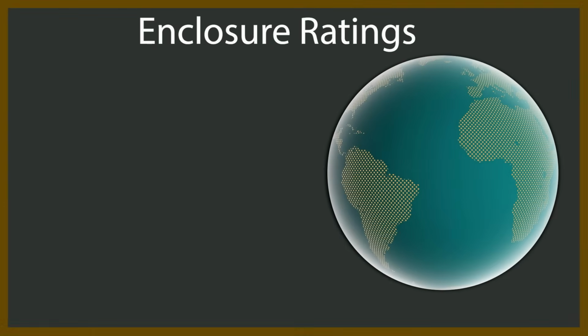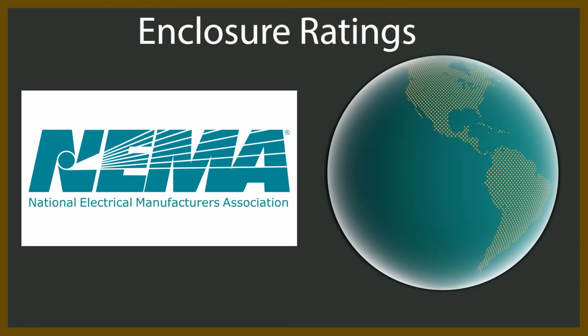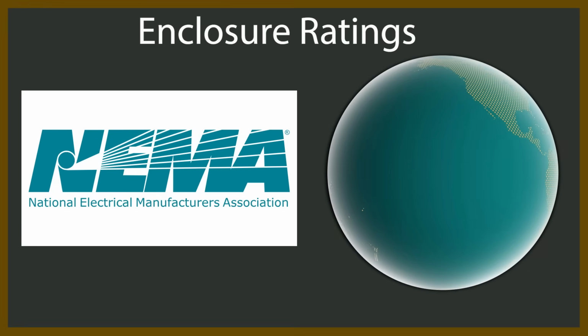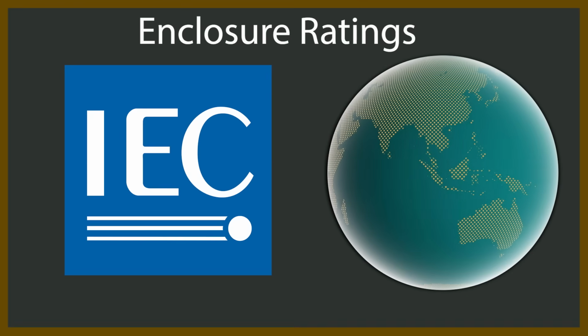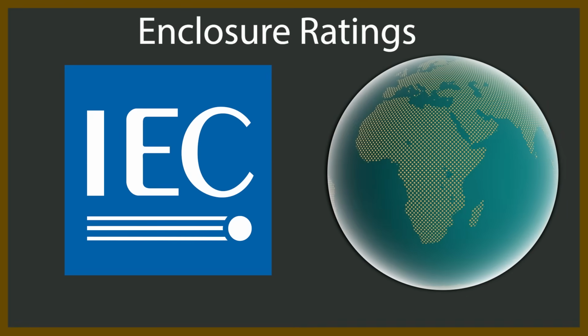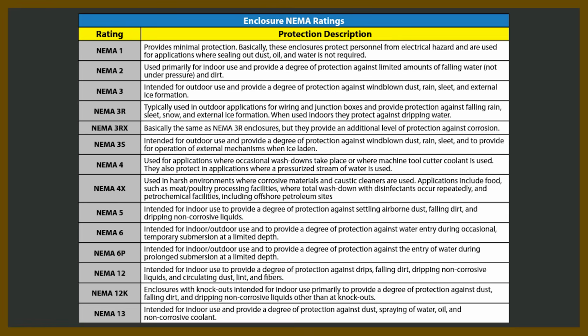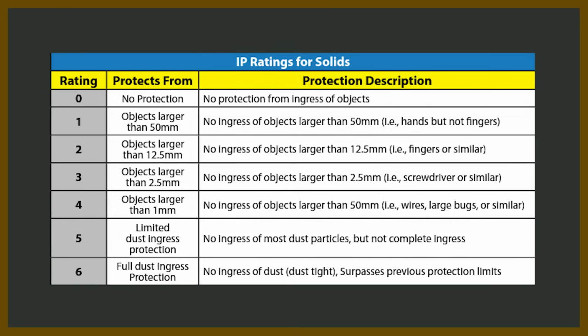Enclosures are rated by two different standards. In North America, they're rated on the NEMA scale. NEMA is the National Electrical Manufacturers Association. Internationally, enclosures are rated by the IEC, the International Electrotechnical Commission, by IP codes or ingress protection ratings. These classify enclosures by the level of protection they offer. Neither group tests these products, but they establish the performance criteria for enclosures intended for specific environments.